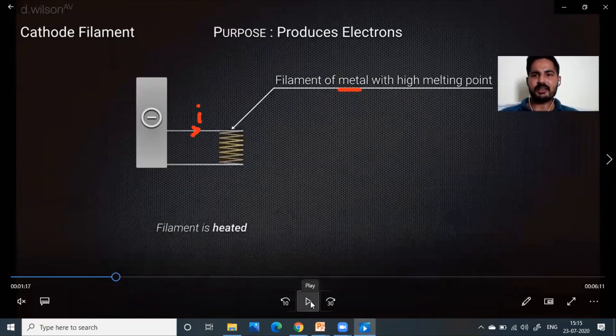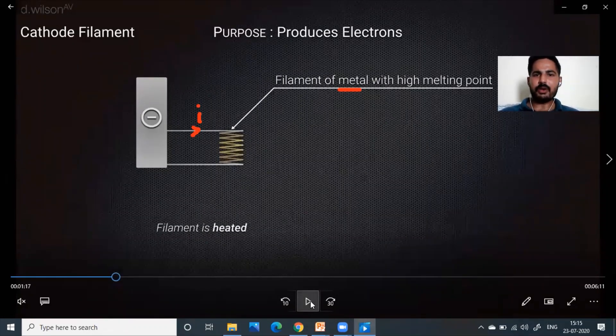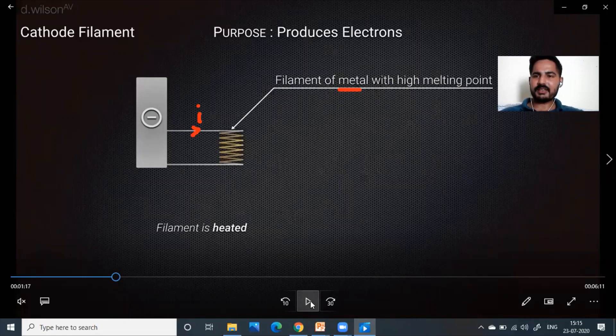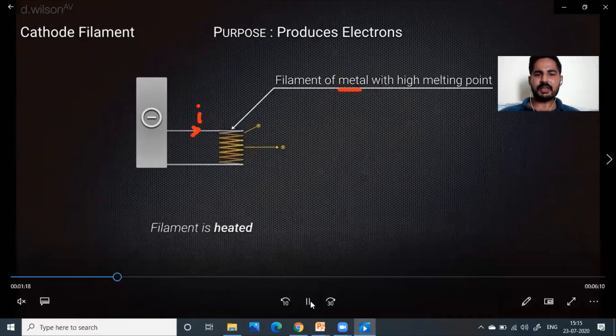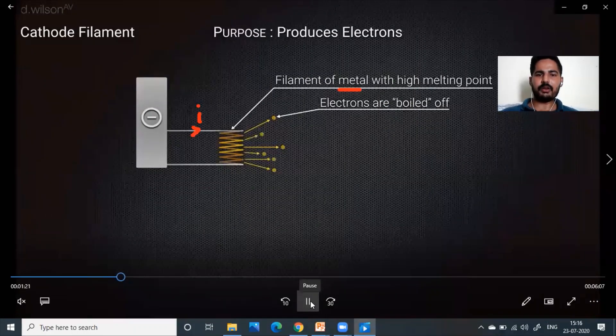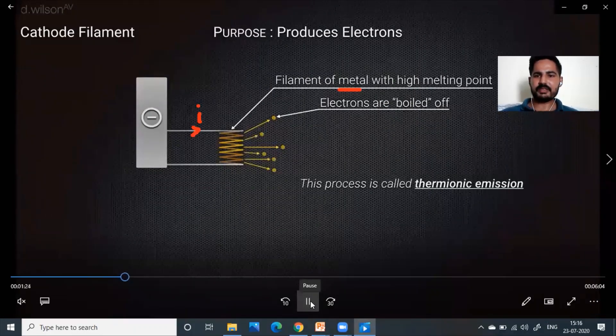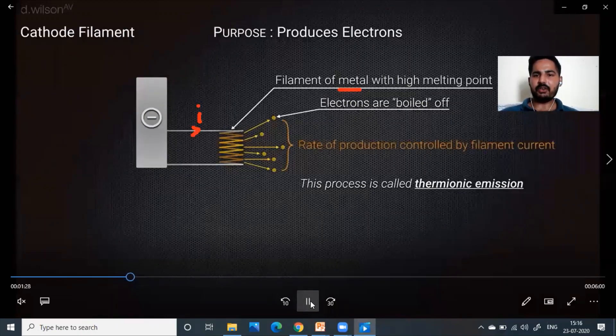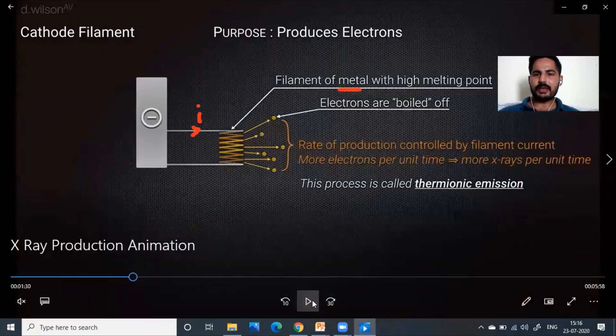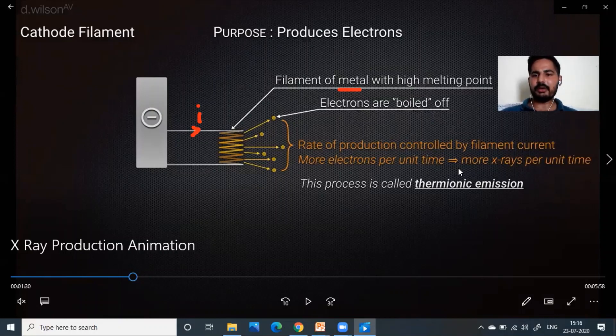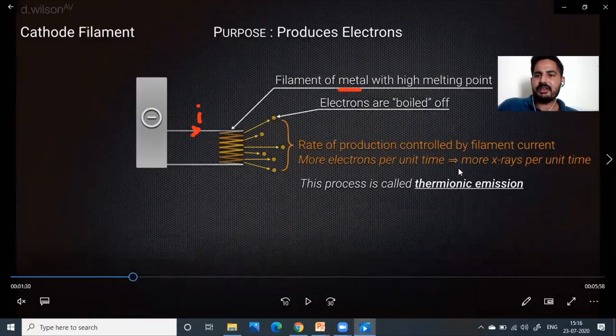How current affects x-rays: when the current increases, the heating increases, which means more electrons will be generated. Those more electrons are going to generate more x-rays. By increasing the current we increase heat, which increases the number of electrons coming out — electrons are boiled off. This is called thermionic emission: emission of electrons due to heating.